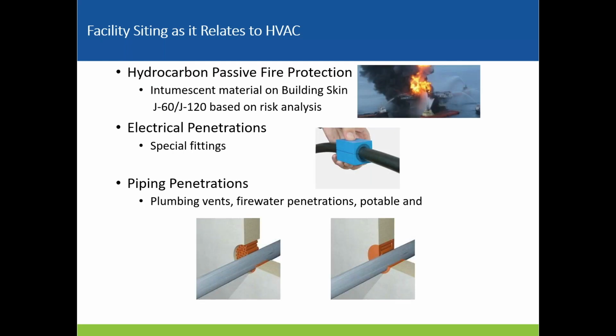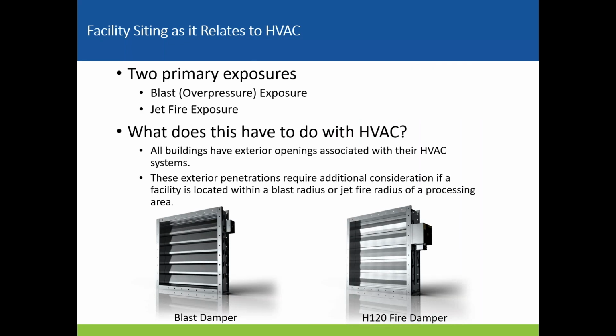So we get into penetrations in these types of structures. You have to use a whole different type of penetration scheme. Really, I'm just pointing this out to you guys. If you ever do a blast resistant control room or something on a platform of this nature, with the J ratings on the building skin, you get into making sure that the plumbing vents, the fire water penetrations, and all of those have the appropriate material that will close in the case of a jet fire, so that it doesn't come through the wall or the space. Our two primary exposures that I generally deal with are the overpressure exposure and the jet fire exposure.